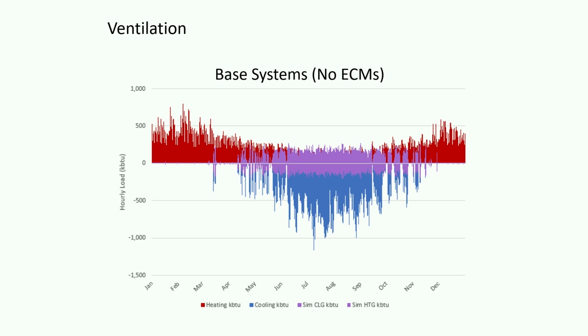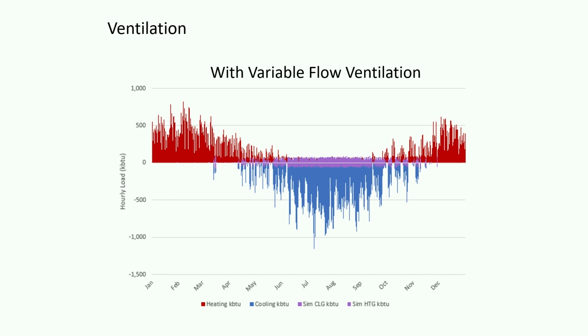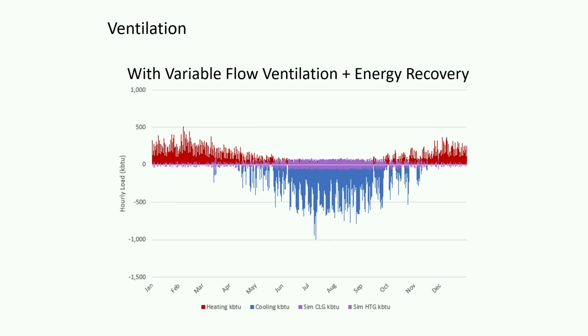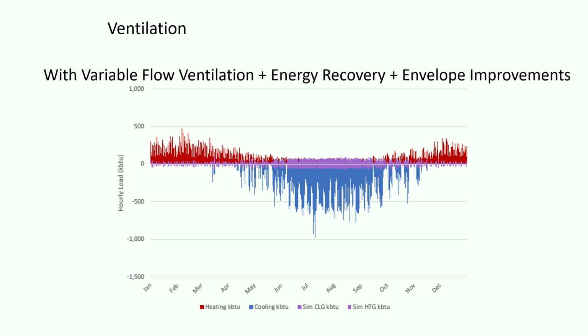Yeah, and this is just some examples of some thermal profiles, without energy conservation measures, doing some variable flow ventilation. You can see the reduction in the load profile, how things change. Not as much heating requirements, but still a lot of cooling. I think Sam's going to touch on that quite a bit, on how that really changes between heating and cooling, okay? And of course, envelope improvements. Envelope is very important. We're seeing some passive house designs, not necessarily in tall buildings, but medium-rise buildings in New York. And it's amazing how much cooling you need and not enough, and you don't hardly need any heating. I mean, it's crazy how that really flips everything on its head when it comes to your thermal profile. So envelope is extremely important in how they're going to build the building.